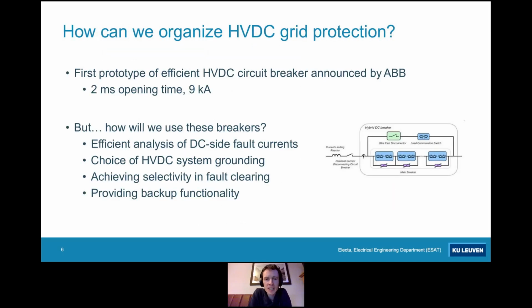Now, at the start of my PhD, ABB had solved a part of the puzzle. They had developed a first prototype for an efficient HVDC circuit breaker that had an opening time of two milliseconds, within the blink of an eye, which they commercialized themselves. And it could interrupt 9 kiloamps. So that's suitable for HVDC grid protection.